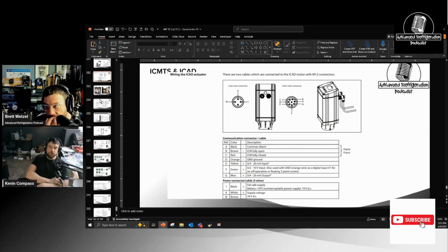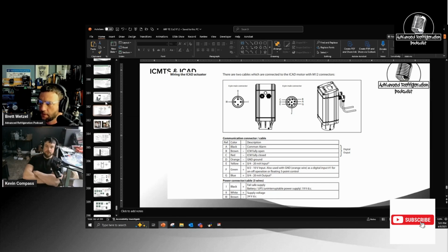So generally the wires for Danfoss are labeled also. Generally. Oh, really? On the plugs, yes. At least on their valves, they're pretty good about labeling the number on the wire. So if you look at the number on the pin, generally corresponds with the number on the wire. Cool. You may have to strip it back a little bit, but you could see the shielding, right? Yeah, the shielding you may have to strip back a little bit, and you could generally see it.